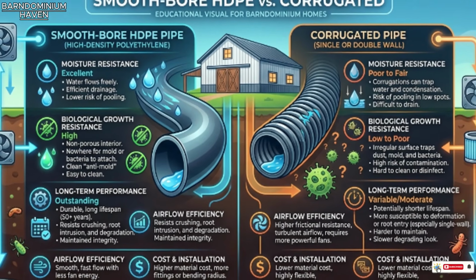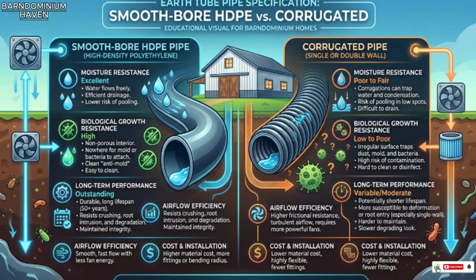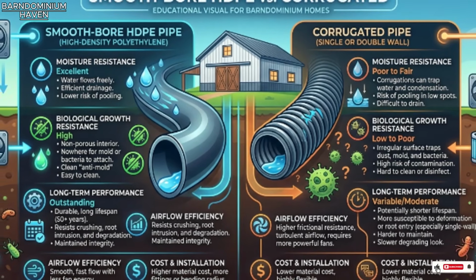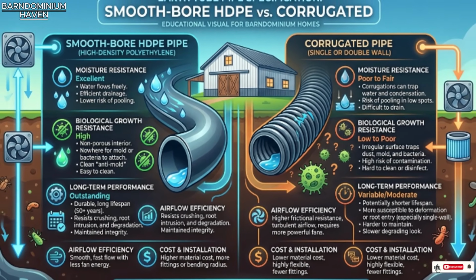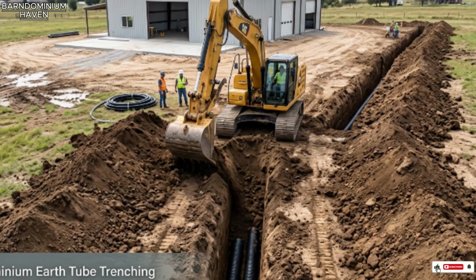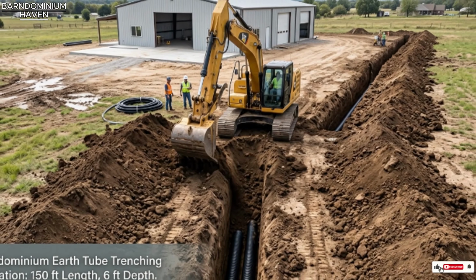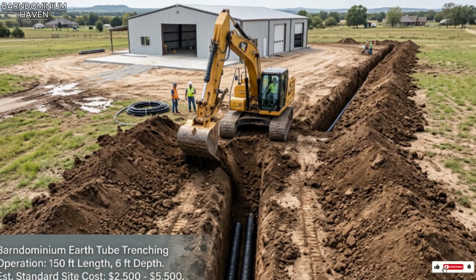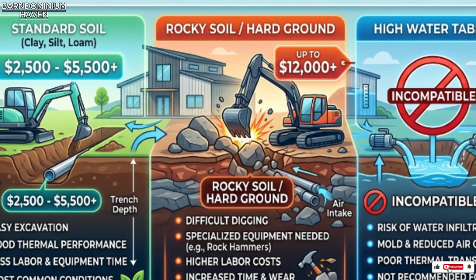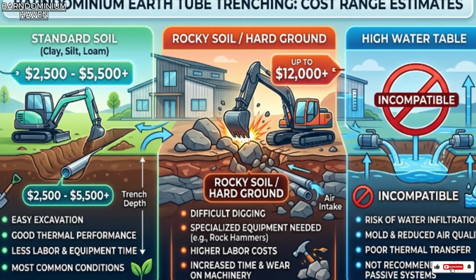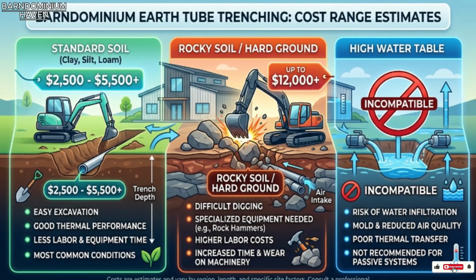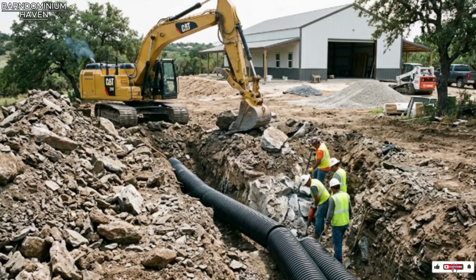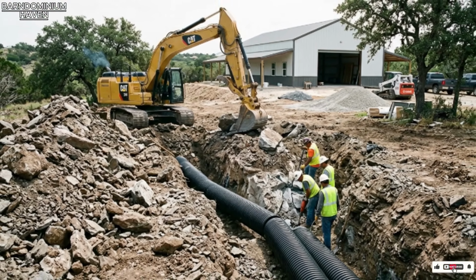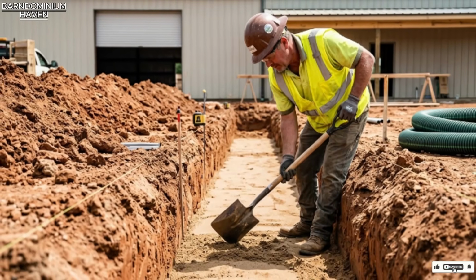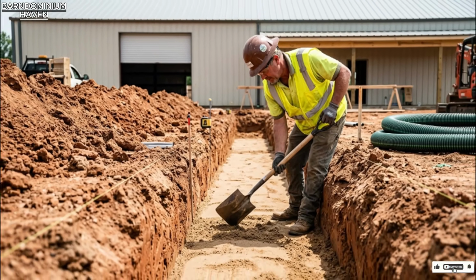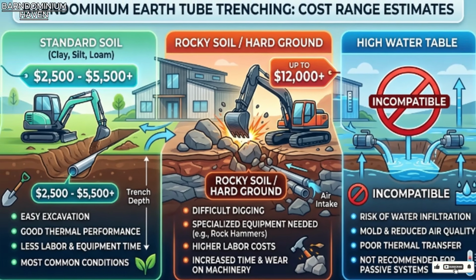The pipe material specification matters significantly. Smoothbore interior surfaces resist moisture accumulation and biological growth more effectively than corrugated pipe. And biological growth inside an earth tube is the primary long-term performance and air quality risk of the system. Trenching, mechanical excavation of a 100 to 200 foot trench at 6 to 10 feet of depth, $2,500 to $5,500 depending on soil conditions, trench depth, and access to the site. Rocky soil, high water table conditions, or limited equipment access can push trenching costs significantly higher. Up to $8,000 to $12,000 in difficult site conditions.